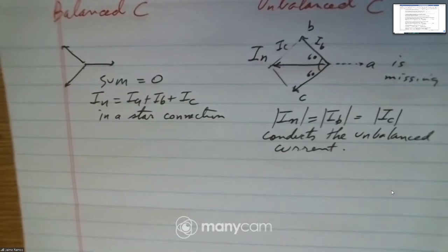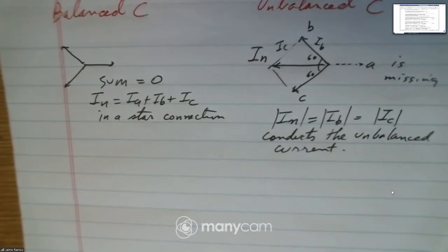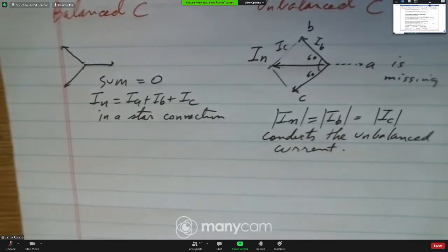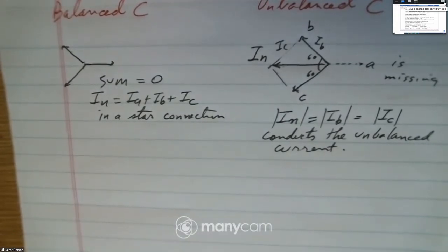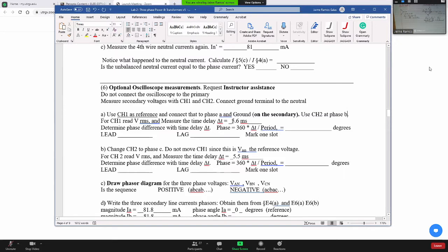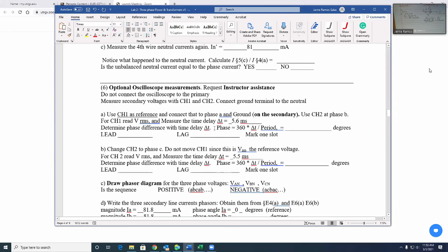So in the first part, A, channel 1 is the reference. That's connected to phase A and ground on the secondary. Channel 2 is phase B, on the secondary. And then measure the time delay. Using the cursors, we measure 5.6 milliseconds. Determine the phase difference with this time delay.